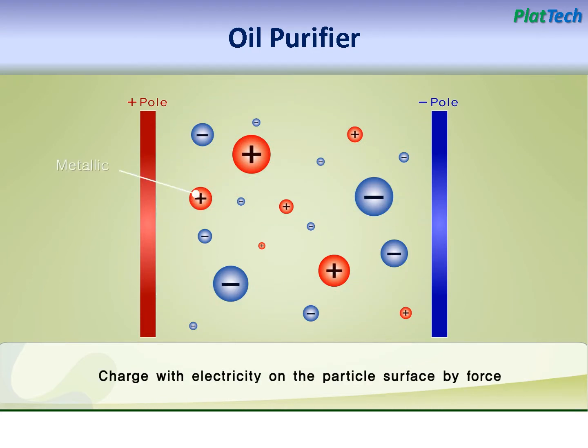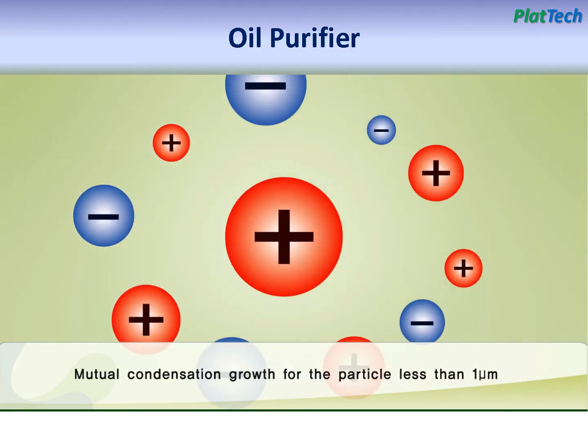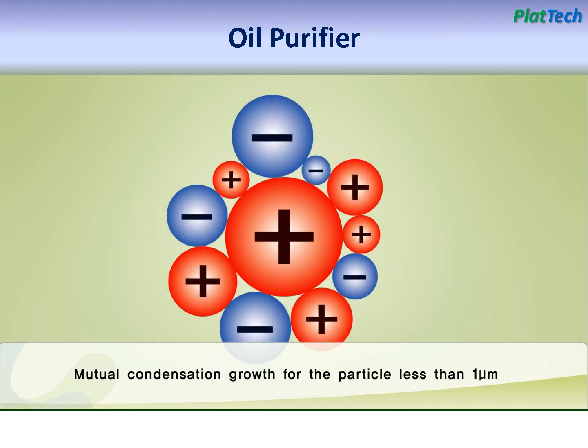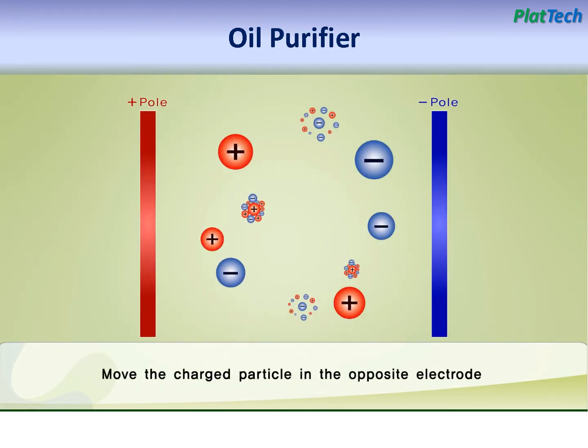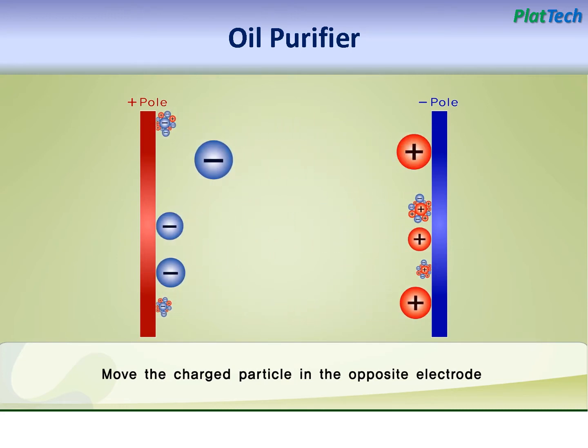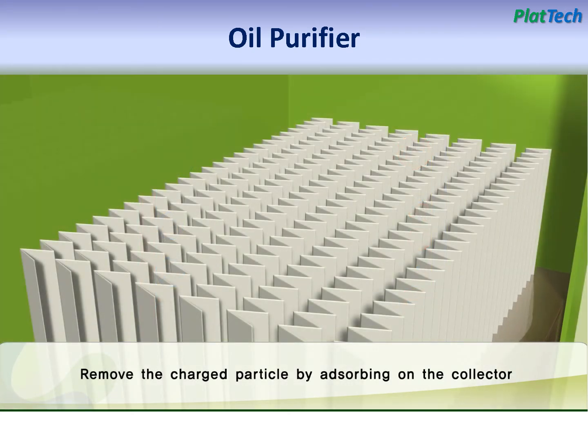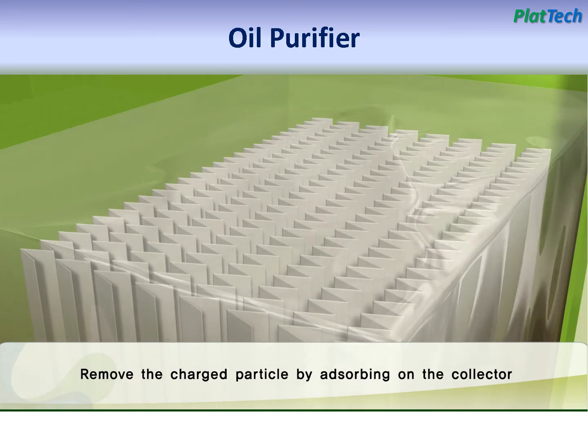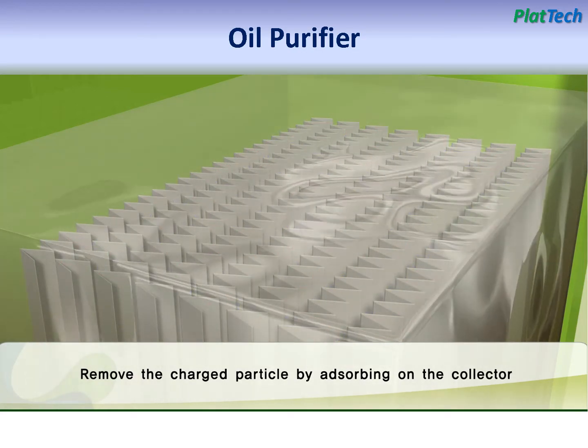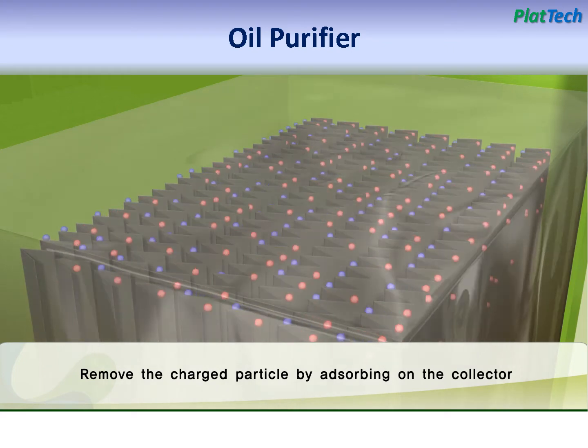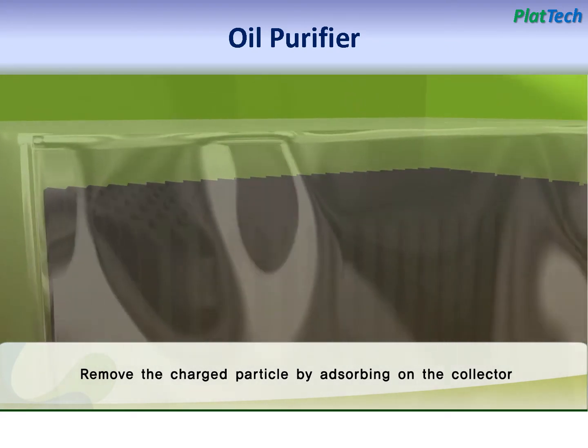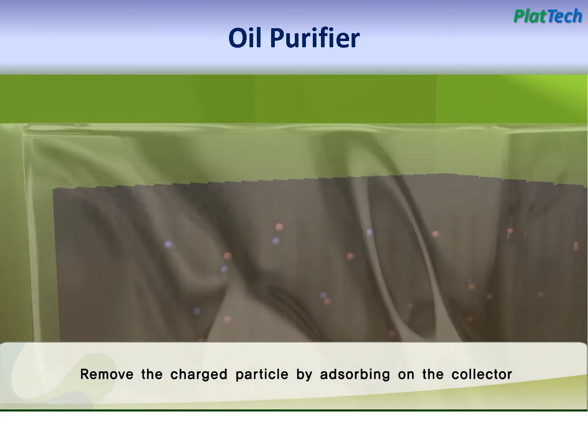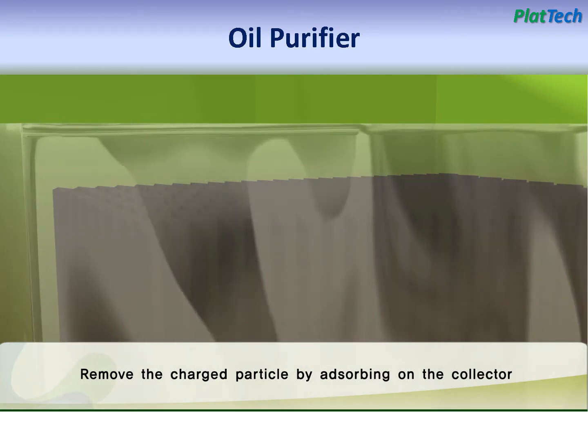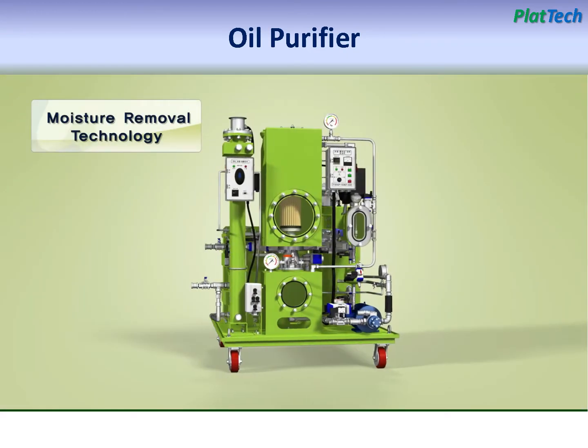There are both metallic and non-metallic ions in contaminated oil, and each ion will be electrically charged. The particle less than 1 micrometer will cohere and grow. Charged particle will then migrate to opposite side of pole. In between each anode and cathode poles, adsorption filter, which is called the collector, is adsorbing particles from the oil. This is one of our unique technologies that can remove particles down to 0.05 micrometer, including the varnish.